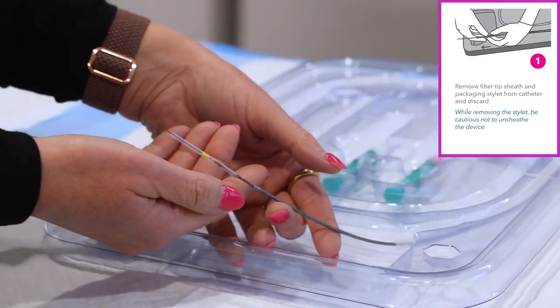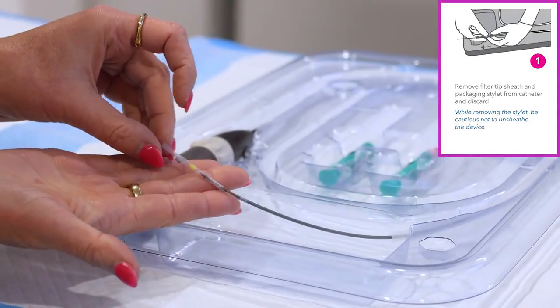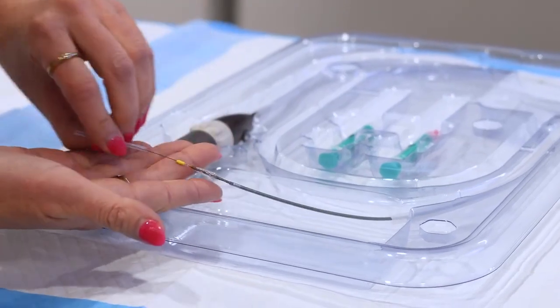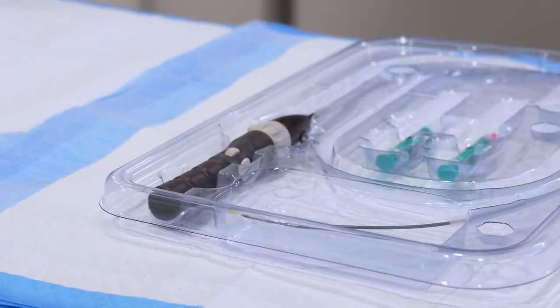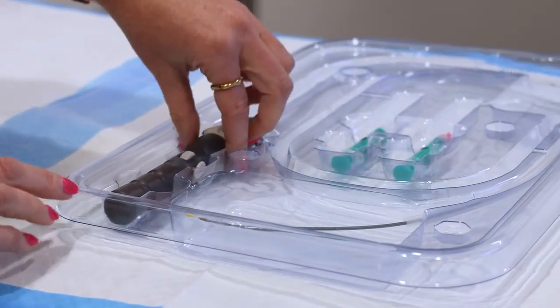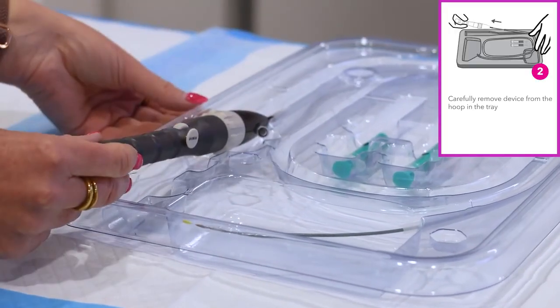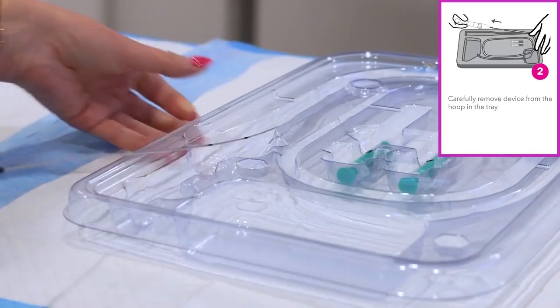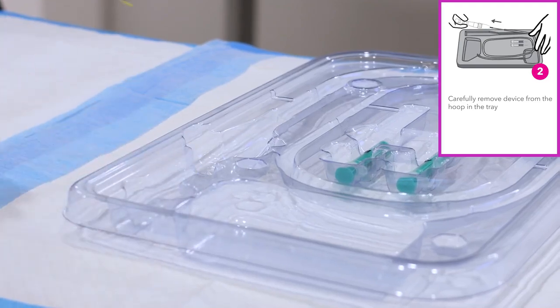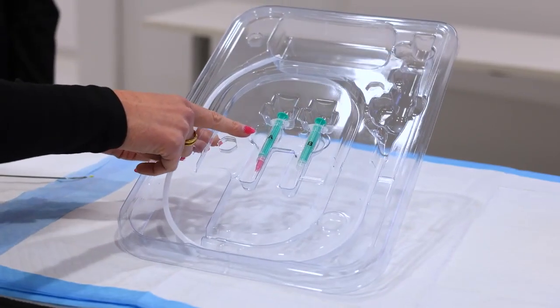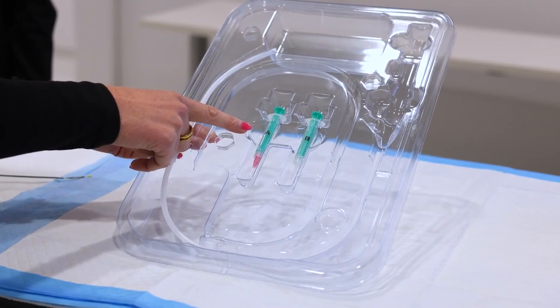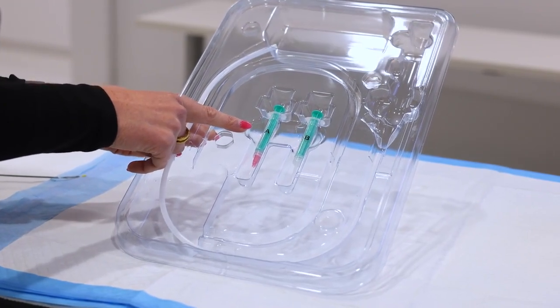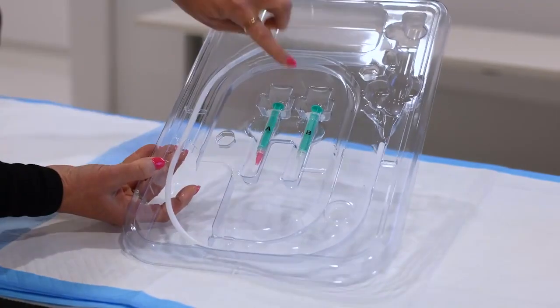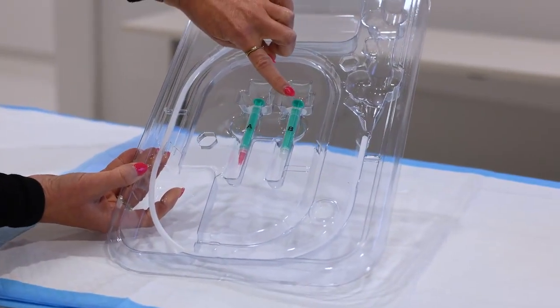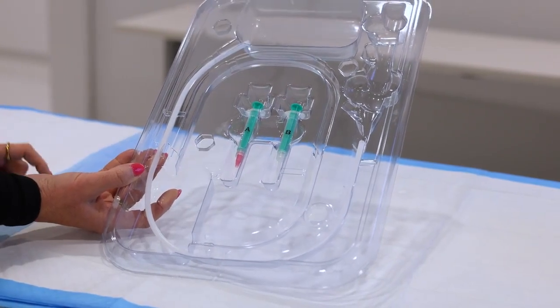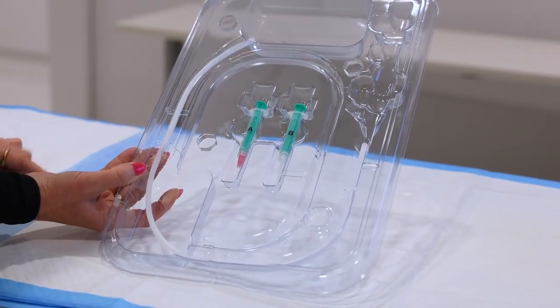Remove the filter protective cover and the metal stylet and discard. Carefully remove the device from the hoop in the tray. Syringe A is a preparation syringe with a filter flushing tip. It is used to flush the filter membrane. Syringe B is a preparation syringe with a catheter flushing tip. It is used to flush the catheter.